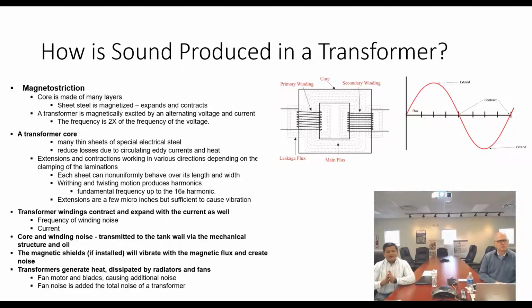During operation, the transformer generates heat, which is distributed by the oil. We also use fans to enhance cooling in the forced cooling method. Fan motors and blades cause additional noise, and the fan noise is added to the transformer noise, and the total overall noise is the transformer noise during operation.